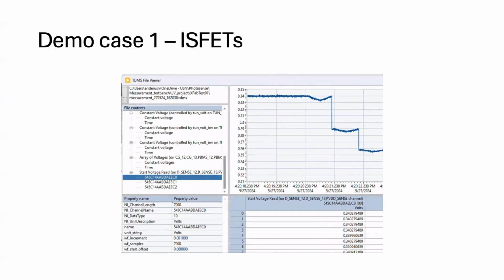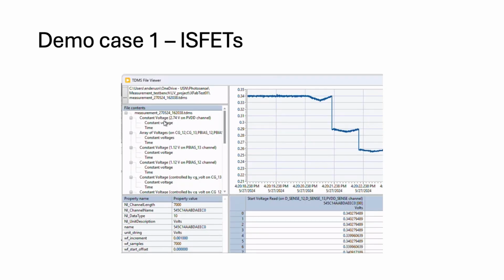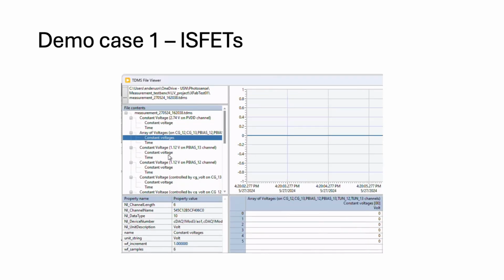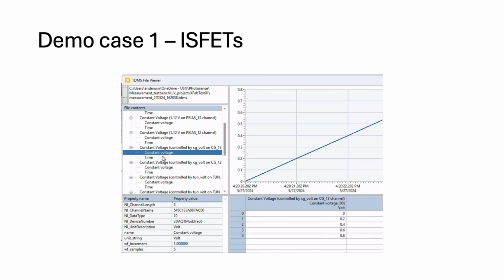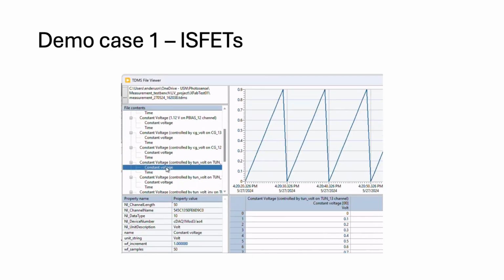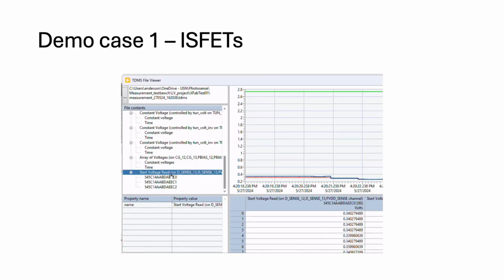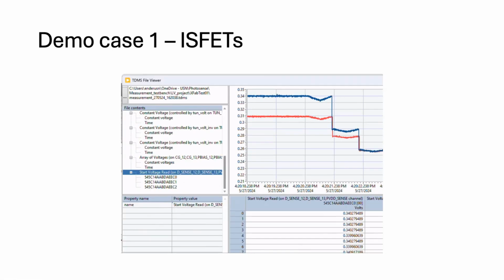I will show you the result more precisely, but here I just wanted to show that everything that happened during the measurement sequence is stored here and can be displayed with the necessary timestamps and so on. Also, all the data is exported to Excel or CSV. So basically, you can then process the data in MATLAB if you want.